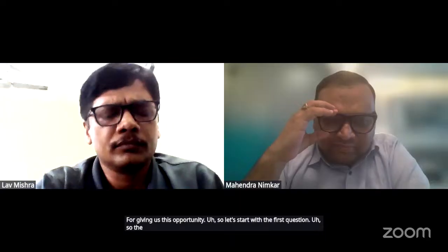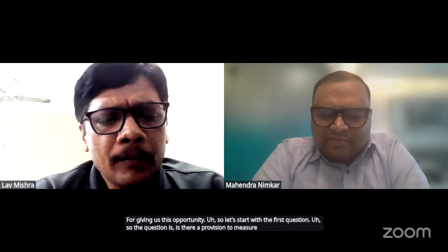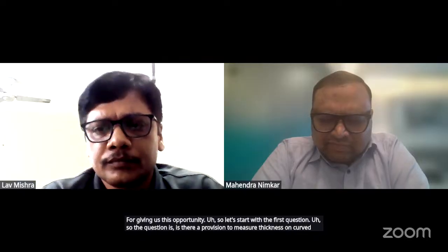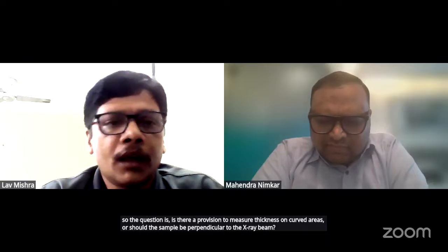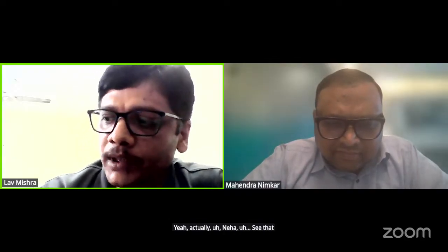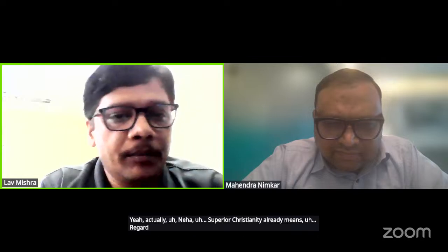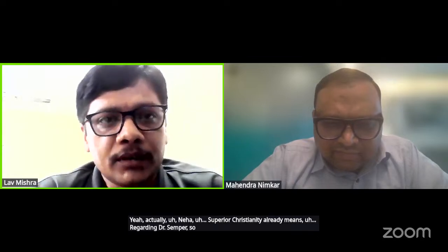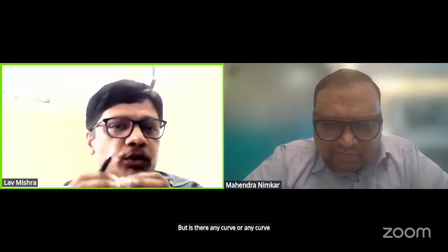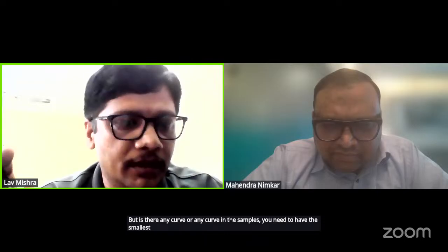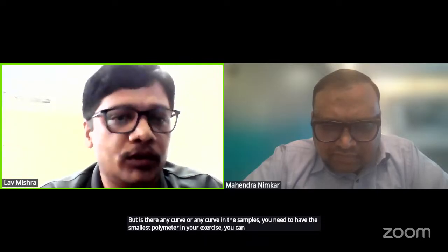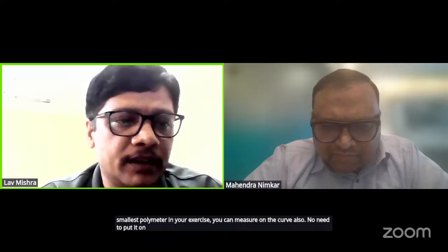Is there a provision to measure thickness on curved areas, or should the sample be perpendicular to the X-ray beam? Actually, Neha, your question is regarding the curved sample. The first principle of XRF is that the sample should be flat. But if there is any curve in the sample, you need to have the smallest collimator with your XRF. You can measure on the curve also. No need to put it perpendicular to the X-ray.